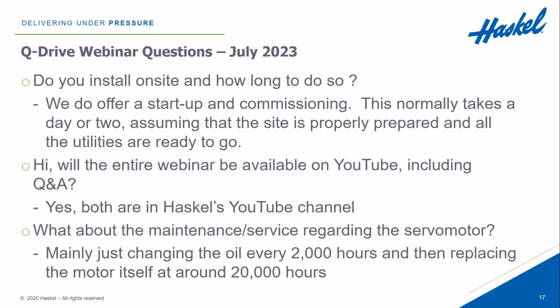Do you install on site and how long to do so? We do offer startup and assistance in commissioning. This normally takes a day or two. We would hope that the customer or a contractor would have the site ready to go, any foundations already in place, and the utilities all run over to that site, gas lines all in place. So all that has to be done is connect it up, put power to it, check phase, and the coolant's there, and the gases are connected up, and we should be ready to go. It can be done very quickly in a day or two.